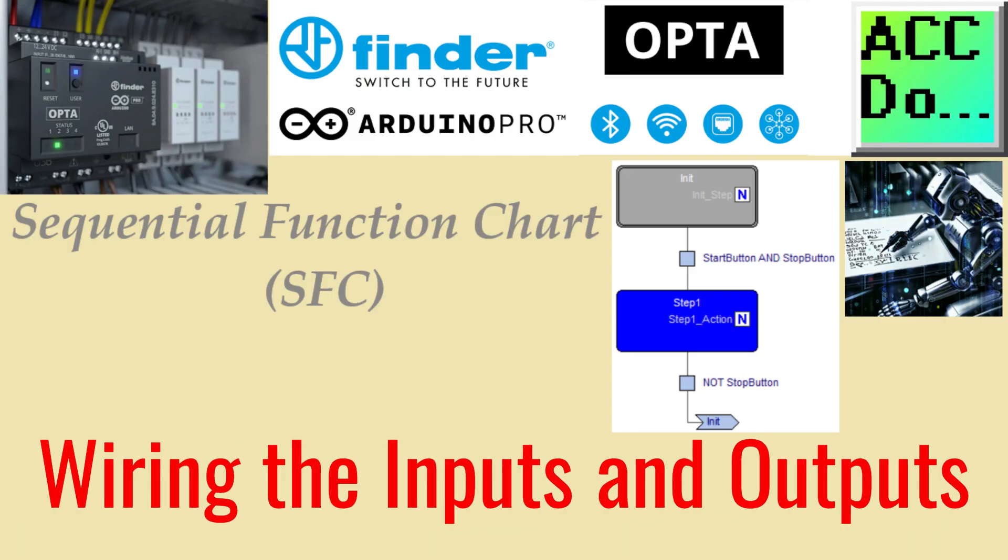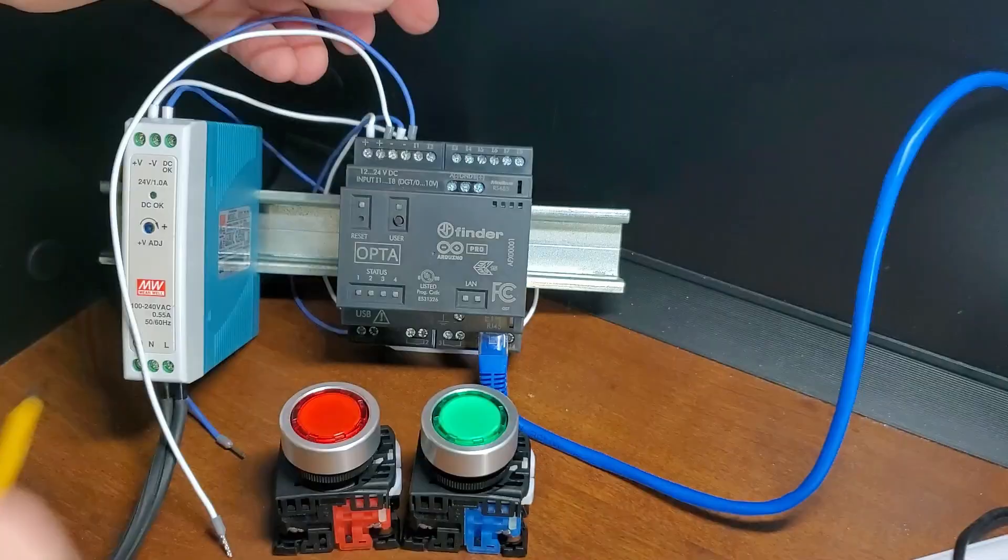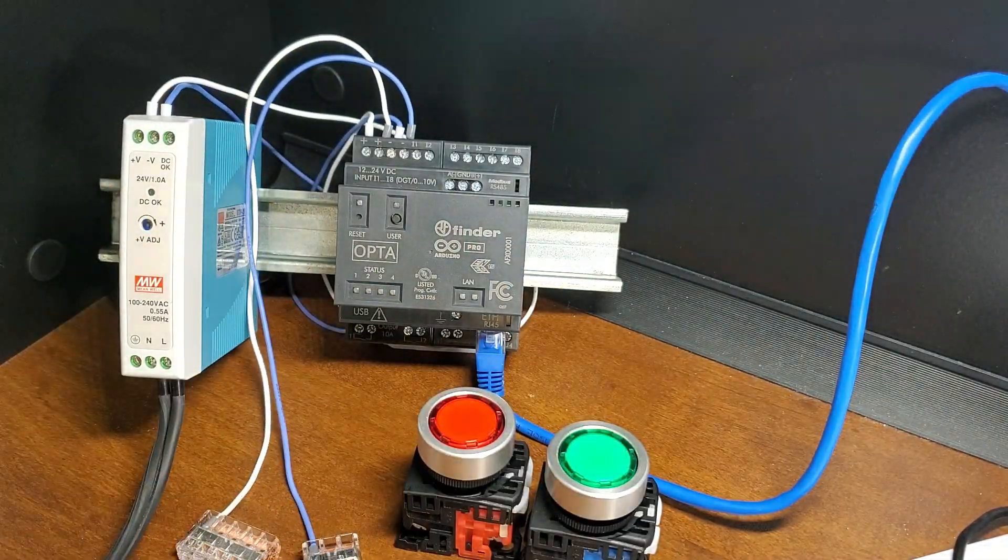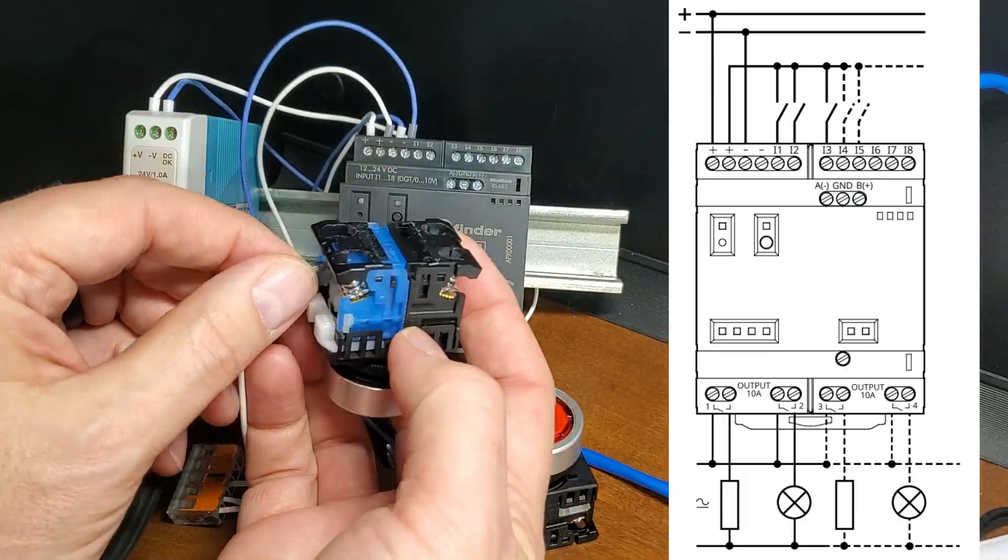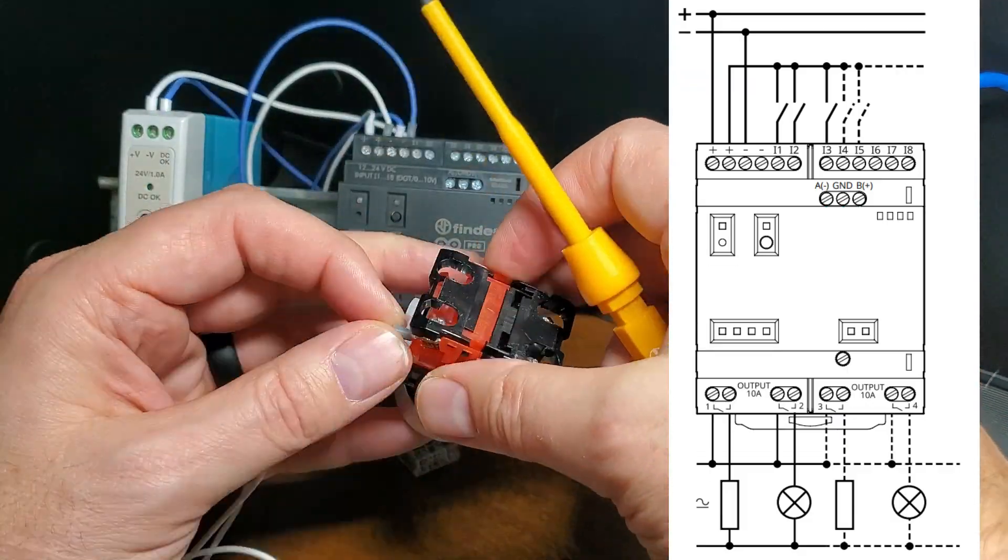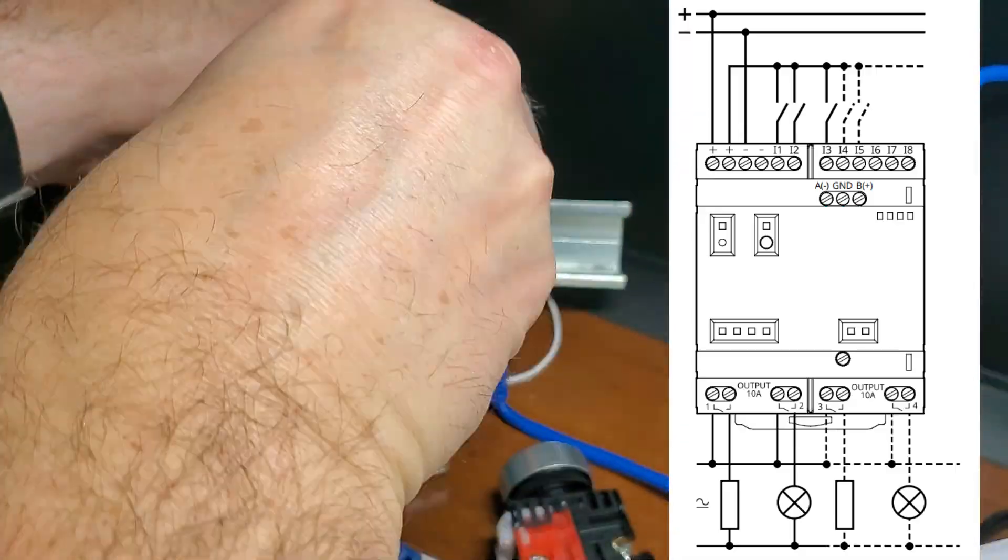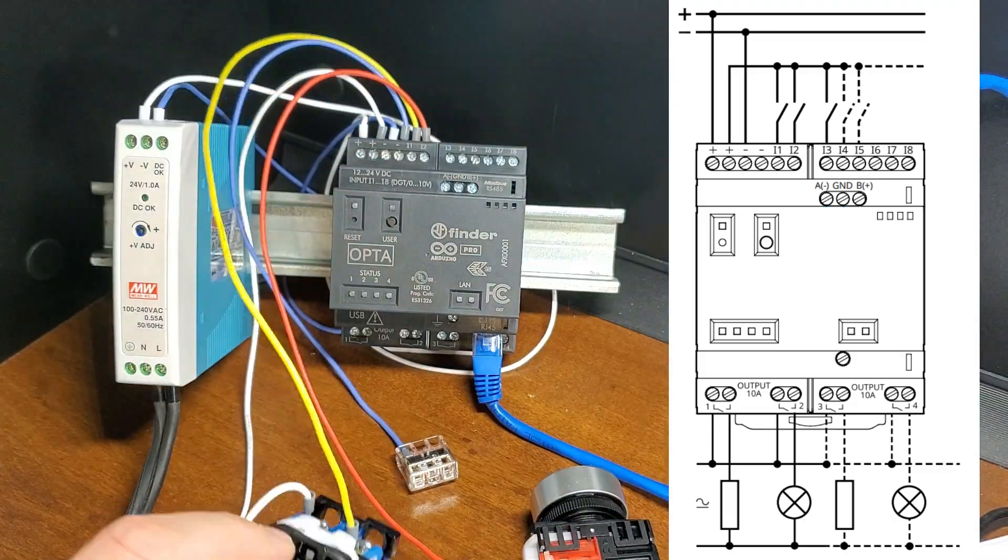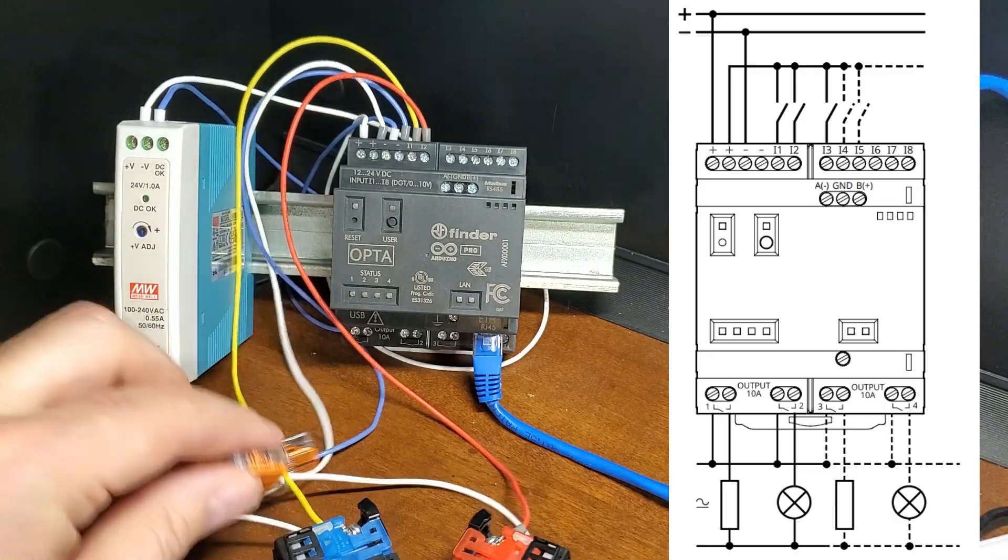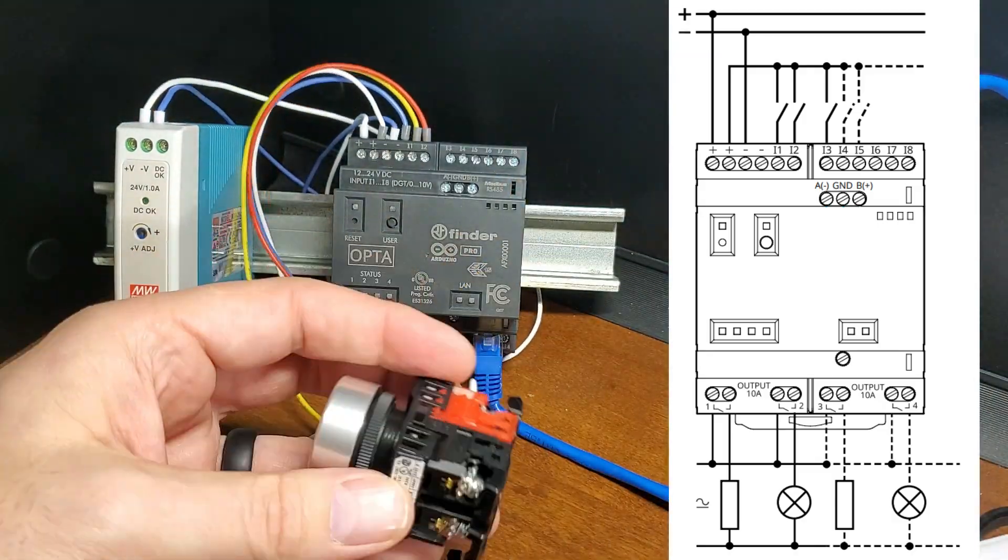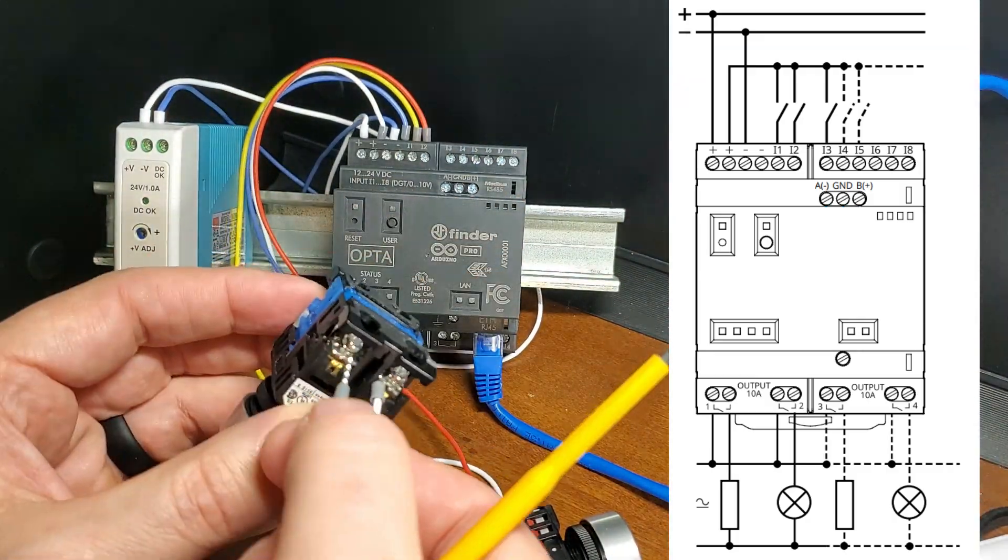We can now physically wire the two lighted pushbutton switches to the inputs and the LEDs of these switches to the outputs. Here is the wiring diagram of the Arduino Opta PLC. The positive 24V DC signal is wired to one side of the green normally open switch contact. It is also wired to one side of the red normally closed switch contact. The other side of the switches are wired to input 1 and 2, respectively. The positive 24V DC signal is wired to one side of the switch lamps.